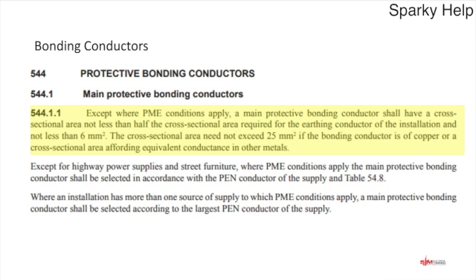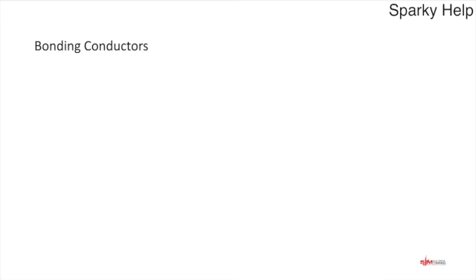However, I will add a caveat on that, and that is the fact that it is on length of run. If your length of run is too high, that may well push your cross-sectional area up because of resistance. However, if you do have a PME installation, then there is a different table for you to look at to make sure you get the right size earthing and bonding in place. So it is very important that we do look at that.